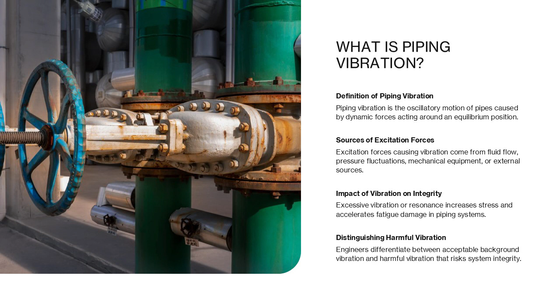Fatigue occurs when cyclic stresses, even if relatively low in magnitude, are applied repeatedly over time. Vibration produces exactly this type of cyclic loading, often at high frequencies, which can rapidly initiate and propagate cracks. One of the most serious consequences of uncontrolled piping vibration is loss of containment.